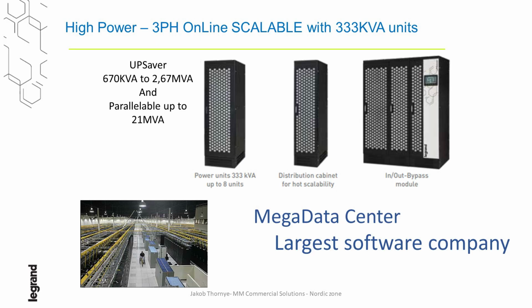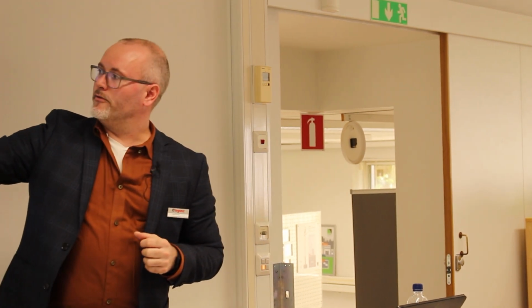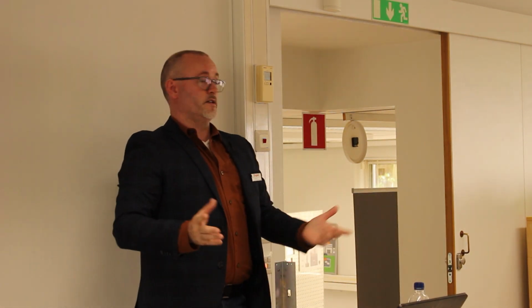This is the Upscaler or Upsaver - a totally scalable system. This is the big brother of the unit we saw before, but it is meant for cases where, for example, in data centers, you can take the full rack. So not only do you take the unit as modular, but you can take the full rack. These come in units of 333 kVA, and you can pull out the full unit and replace the full unit for data centers or very big hospitals in this sense. So this is not only modular based inside as we had in the other cabinets, but even the full units can be replaced.